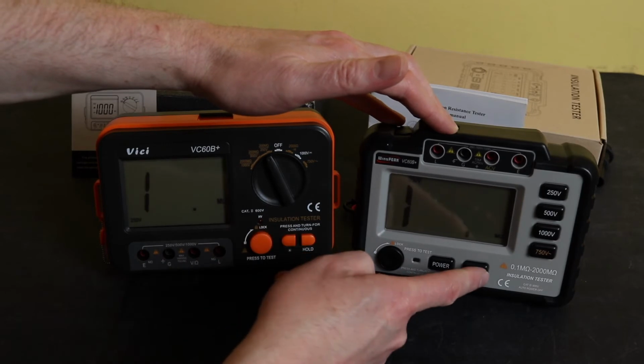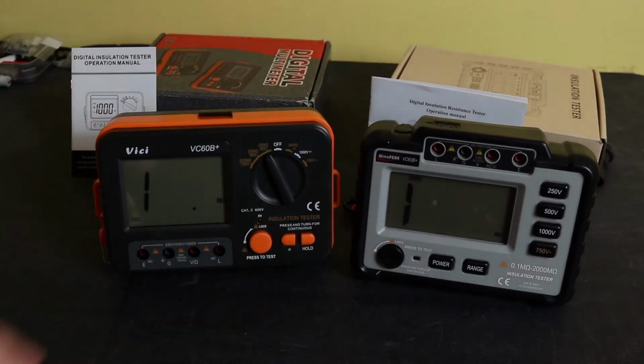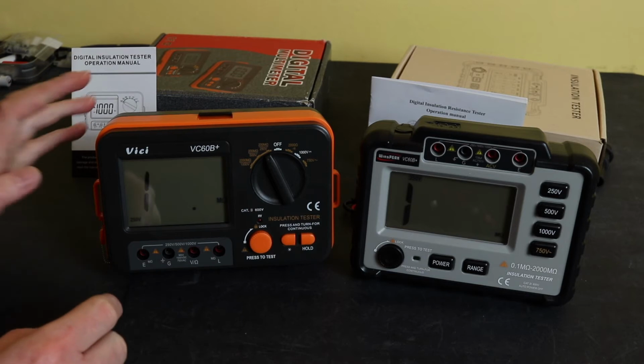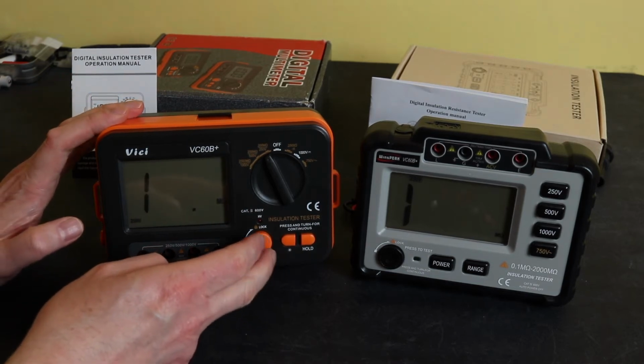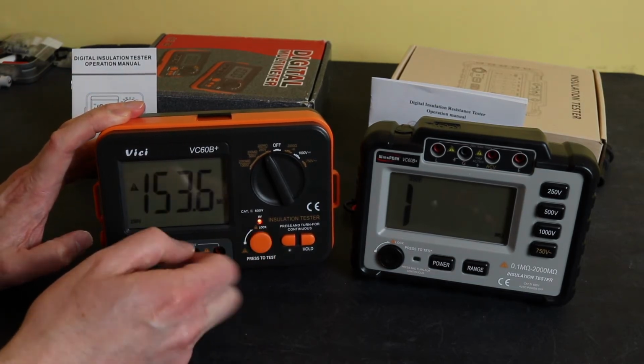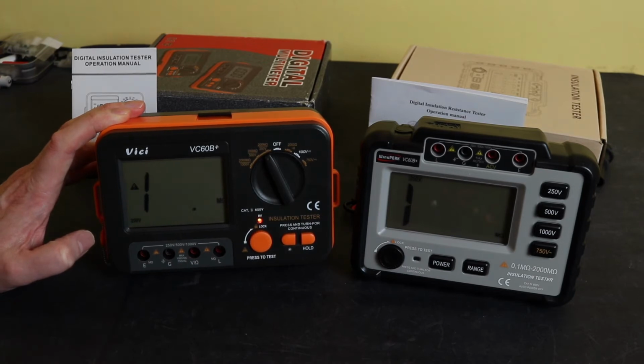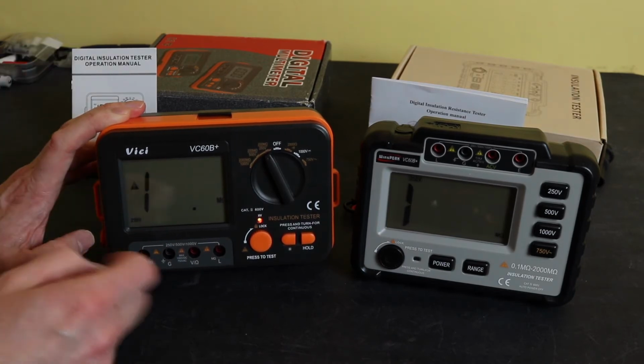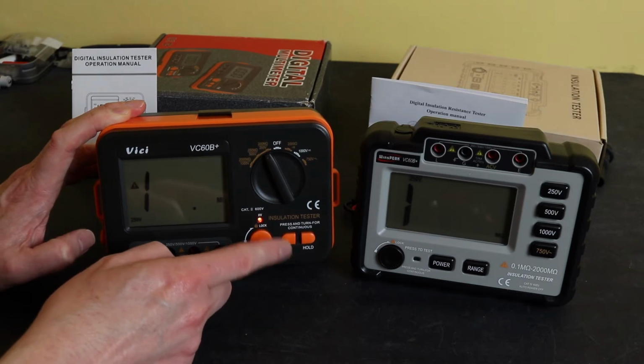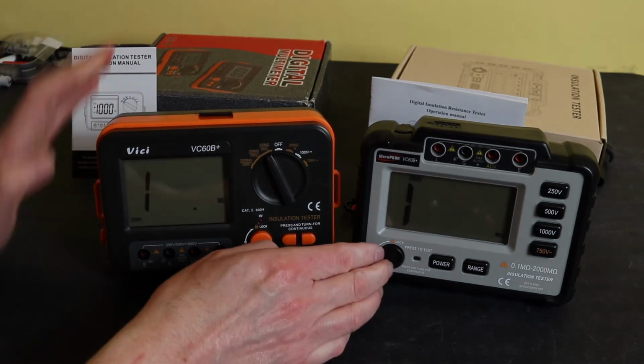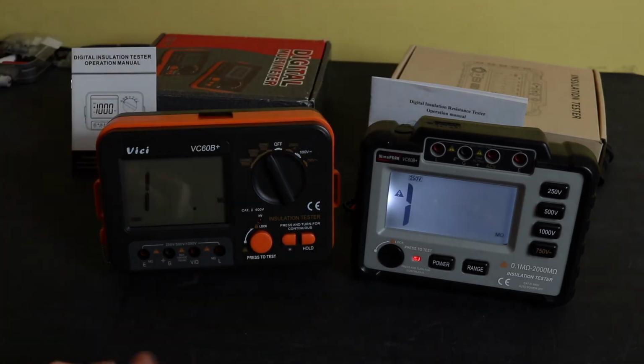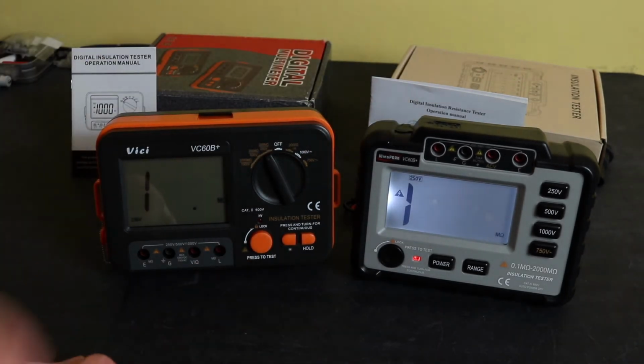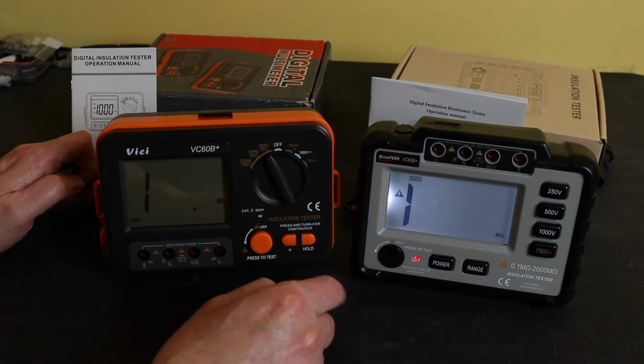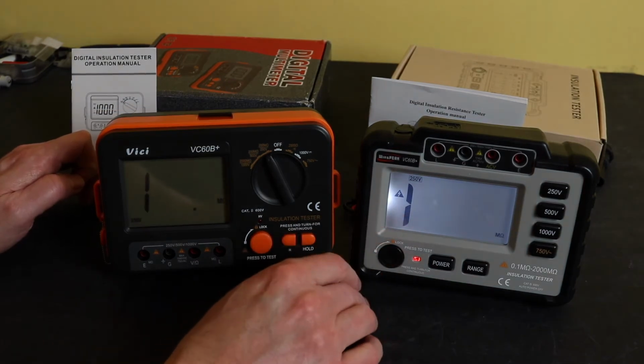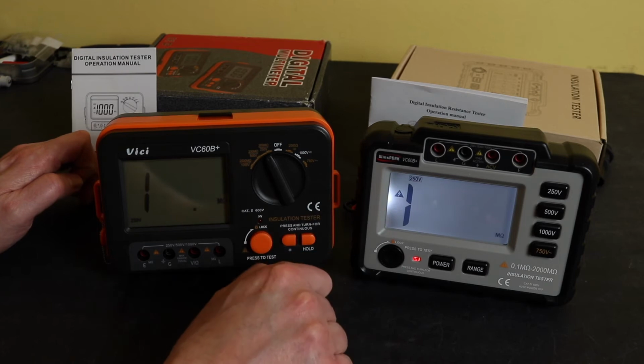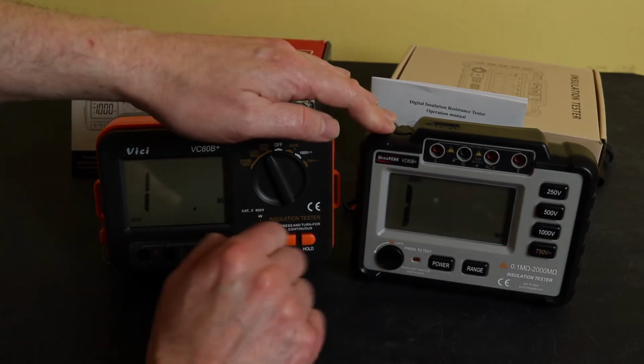Take it down to the lower range, or press it, take it up to the higher range. Both insulation testers have twist to lock functions, so when you're testing you can push it on and twist it to lock it in. This has a permanent alarm that you can hear going off when you put it into test. And this one here, as you saw earlier, doesn't have an alarm at all, but again you can twist and lock. And both of them have a little LED to say that the test voltage is on, and the little test symbol comes up on the side of the screen there as well.